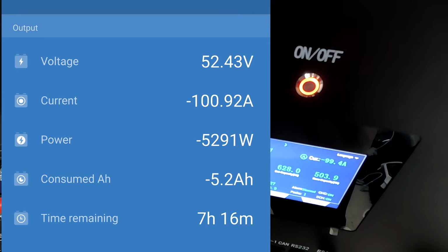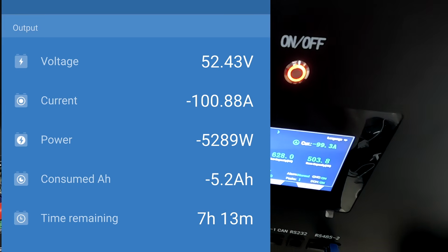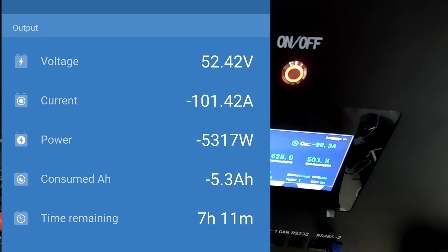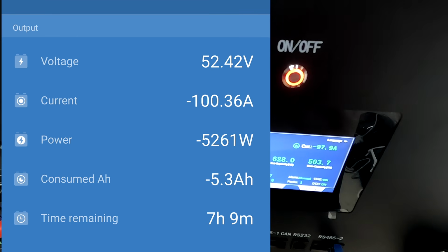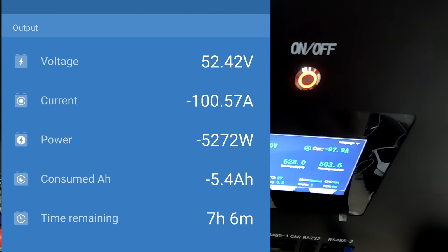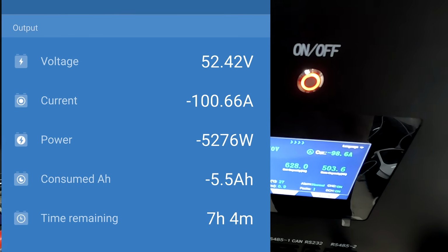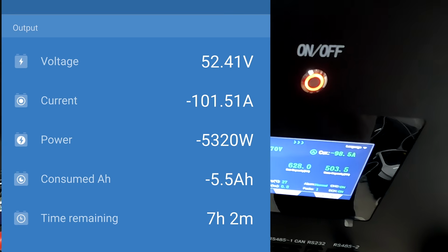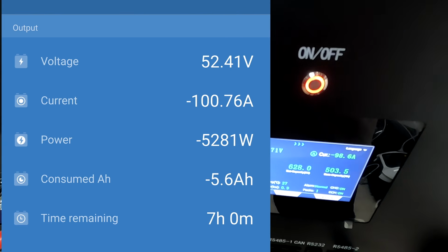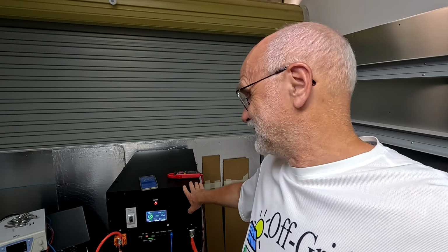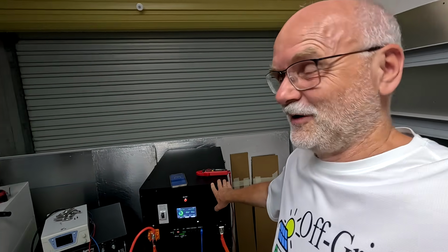I think I want to leave this here just in case some other loads are coming on. I don't want to overload anything and having this 63 amp circuit breaker tripping. So we discharge the battery with 100 amps. And the smart shunt claims it will take 7 hours and 2 minutes, which could be correct. It could be even longer because we know this is not 628 ampere hours. This might be more than 670, 680 ampere hours or so. So it will take a long time, yeah.